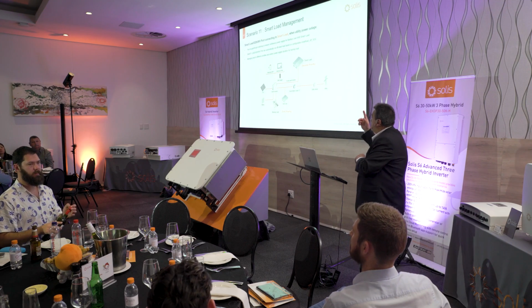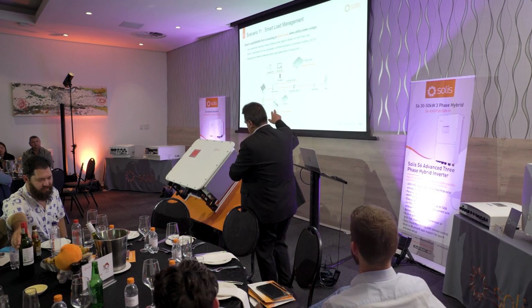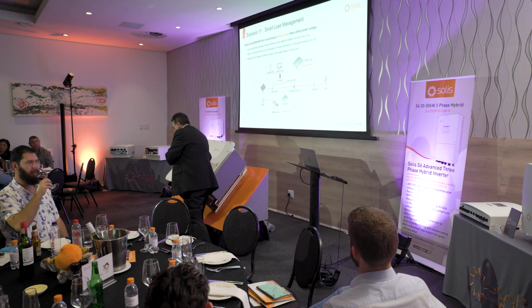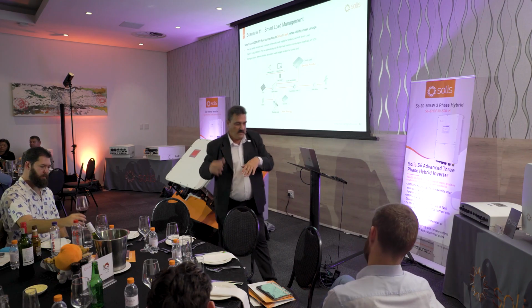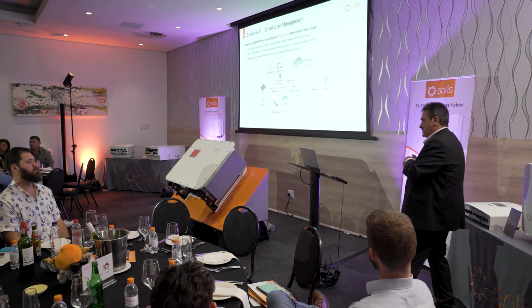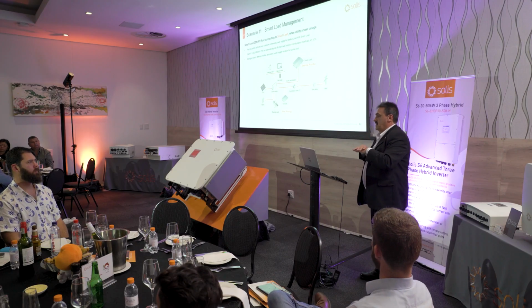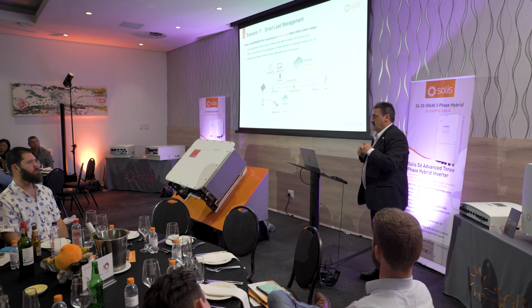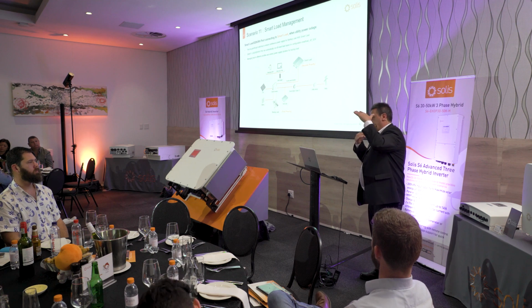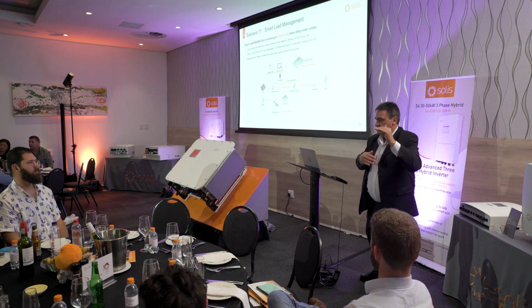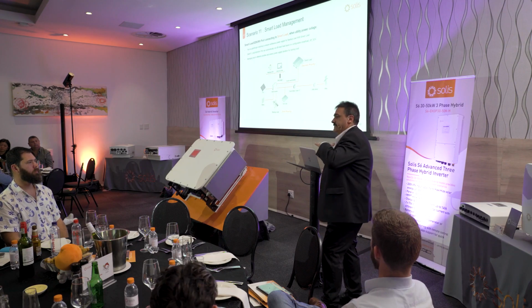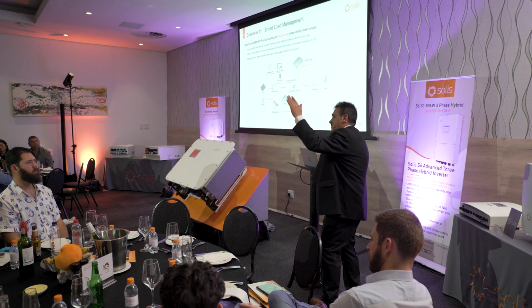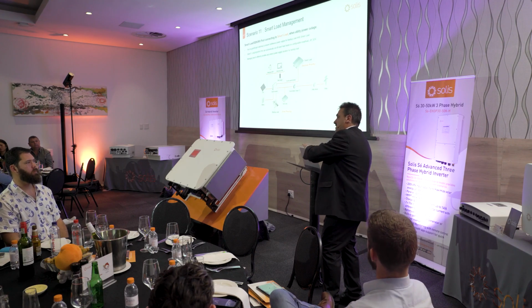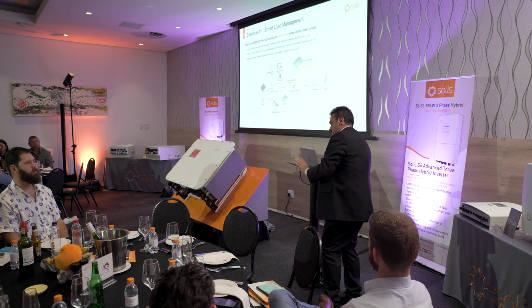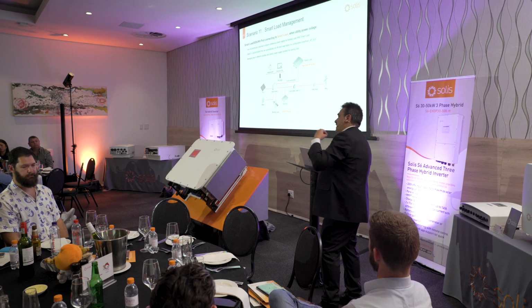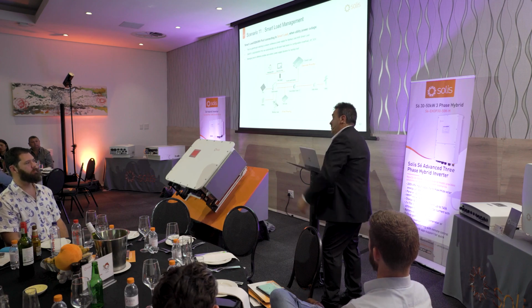Okay? So the reserve SOC setting in the system will stop any discharge function, whether it is timed or not through the time of use. But when it gets to that reserved SOC function, it will override all of those. Okay? So that you have that energy security stored in your battery for when those outages do come. Right? So that's like a control point. Right? And all those things, all the time of use and the SOC settings, those are all control points that you carefully work out and say, I want this, I want this, I want this, and you're telling this machine, this is how I want you to operate. And it gives you all those tools to make it do so.